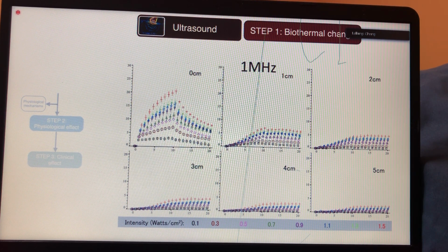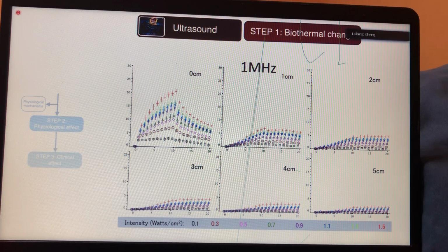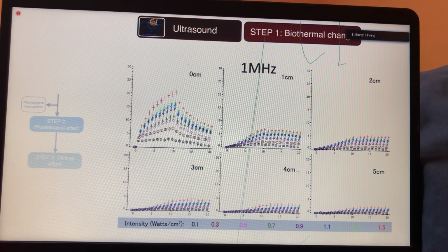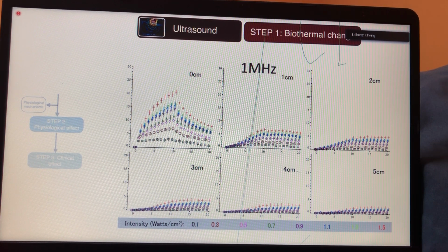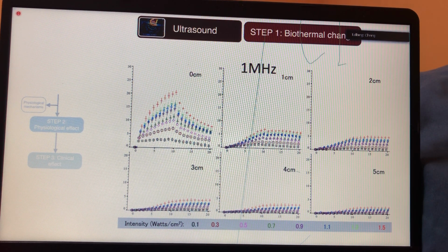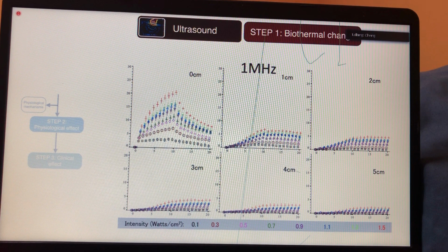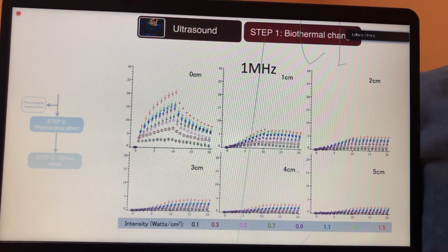The peak was actually somewhere around just before 20 minutes. So that 3 pattern you have to bear in mind. Those 3 patterns will help you to decide on how long you want to heat the tissue and where your therapeutic window is. For the skin, as long as you're giving the treatment, the therapeutic window is while the treatment is on. The minute you switch off, you lose all the energy, it starts to cool down.